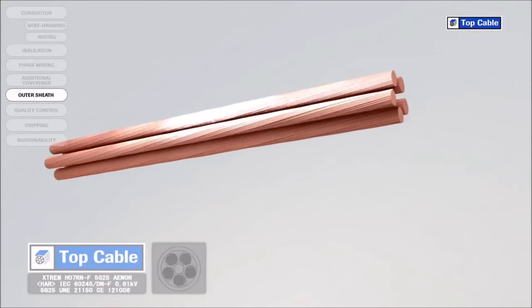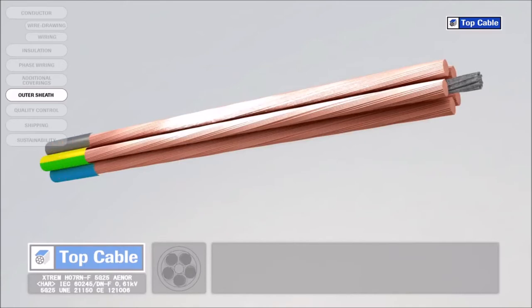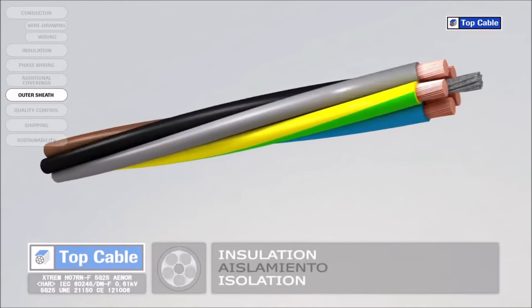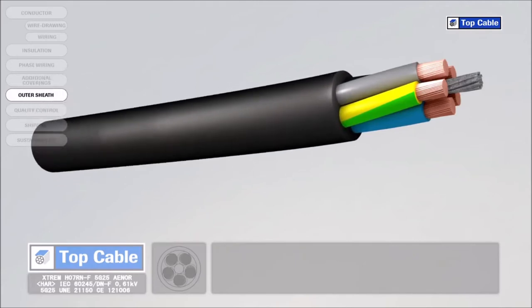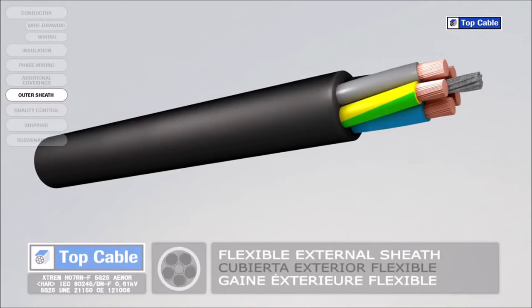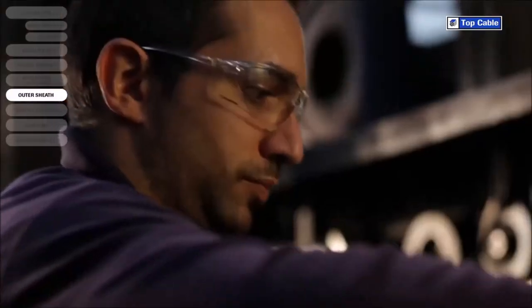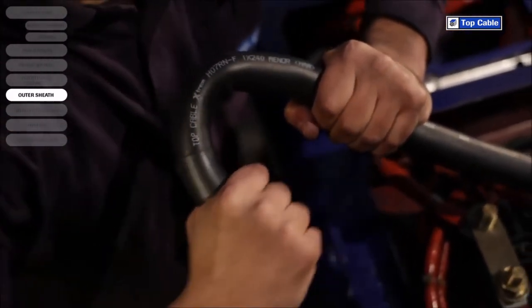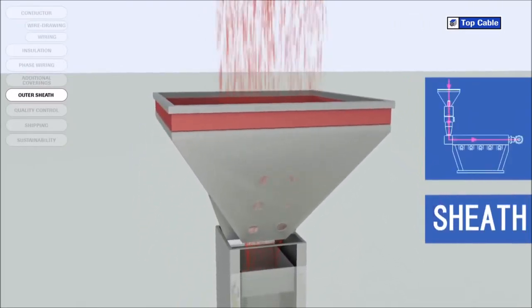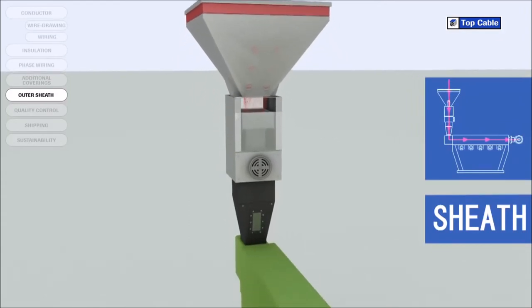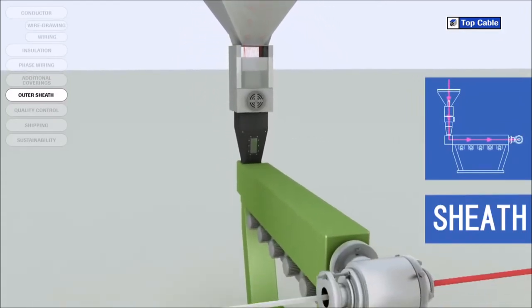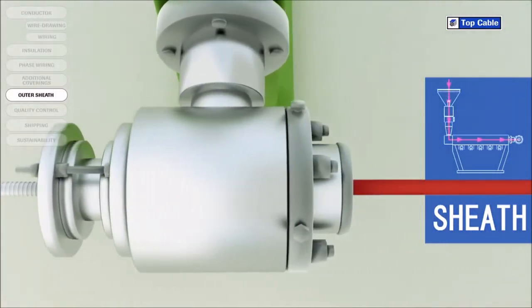Cables usually have an outer polymer covering for protection, called the outer sheath. The sheath protects the conductors and their insulation from external elements which may change their electrical properties, such as moisture. It also protects them from mechanical aggression which may occur during the installation of the cable. As with the insulation, the outer sheath can be made from a thermoplastic or a thermosetting plastic. The outer sheath is applied like the insulation via a process of extrusion at high temperature. The sheath may be made from different materials depending on the required protection level, the final flexibility of the cable, and the work environment.